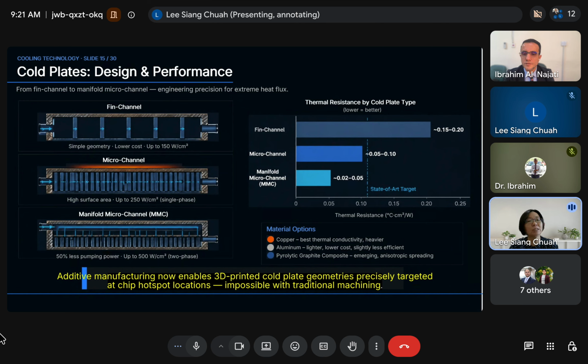The material choice is also critical. People are using copper, aluminum, or graphite composites. And the major breakthrough is additive manufacturing, which enables the cold plate to be tailored to the chip hotspots and deliver the cooling exactly where it is needed. So cold plates are no longer just a cooling component. They are engineered to match the specific heat and design requirements.